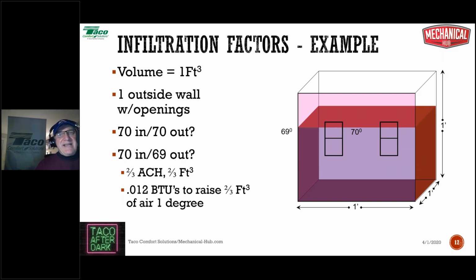Now, IBR built some test houses with the University of Chicago many, many years ago, and they tested air leakage rates. What they found was, and again this is a generalization, a room with one outside wall with an opening will have 2/3 of an air change per hour. So what that means is in this room, 2/3 of a cubic foot of 70 degree air is going to leak from inside to outside over the course of an hour. And the same amount of air, 2/3 of a cubic foot of 69 degree air, is going to leak back in, going from outside to inside to replace it.